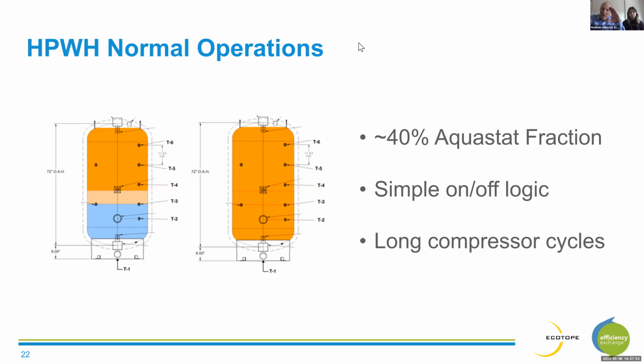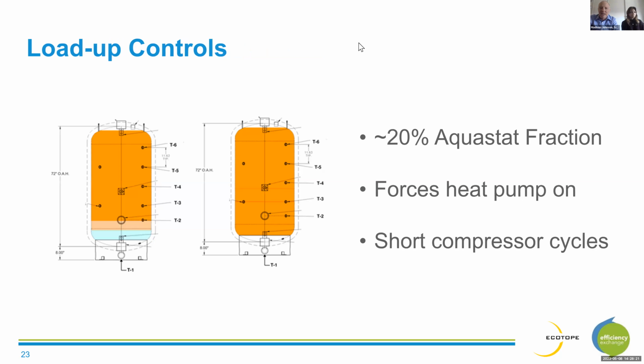And then it recovers that bottom 40% of the tank. And so it has a pretty long compressor cycle, which compressors like to do. They don't like to turn on and off a lot. And so what we did, in cooperation with Mitsubishi, is instead of using a single aquastat location to turn their heat pump on and off, we put 5 aquastats at various levels in the tanks.